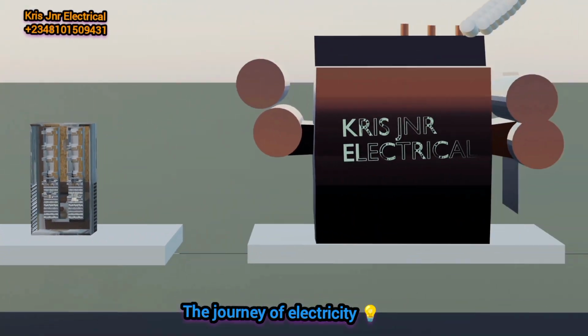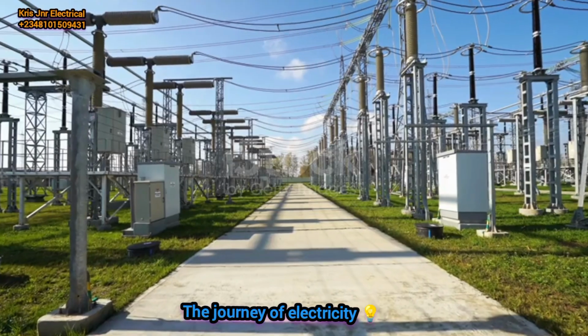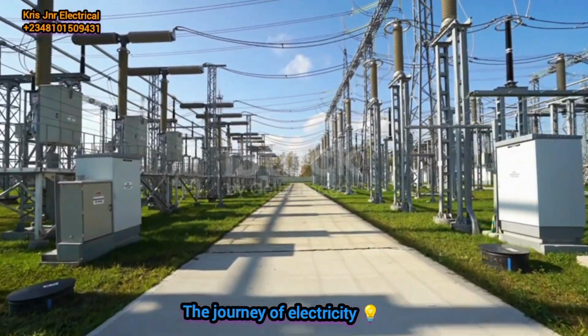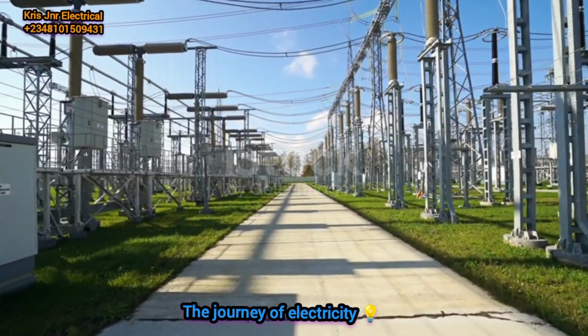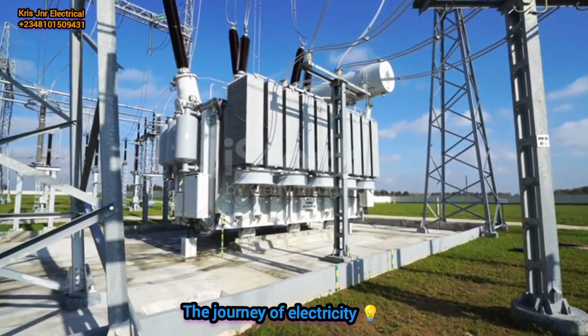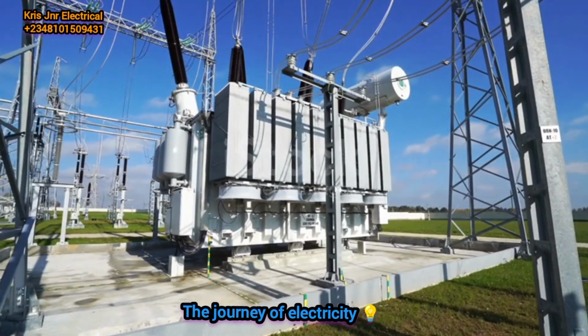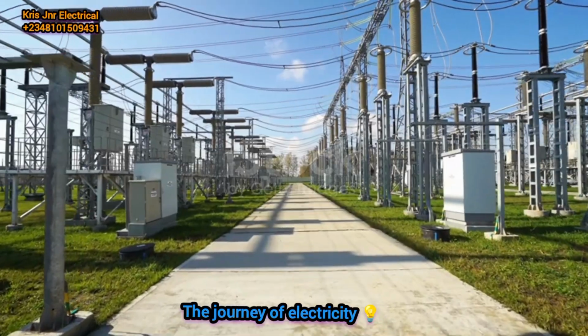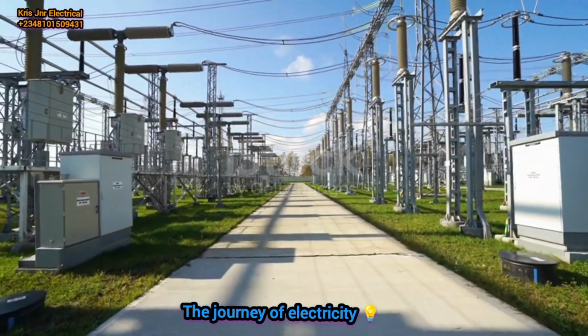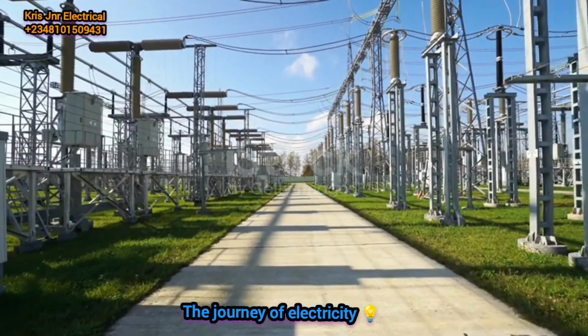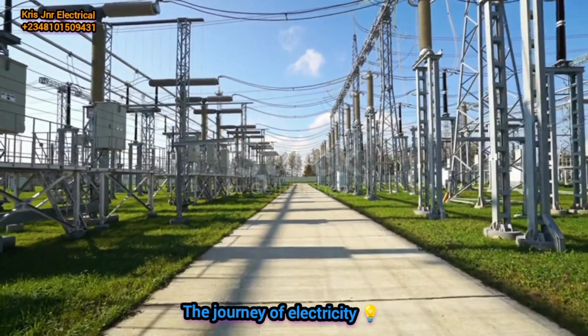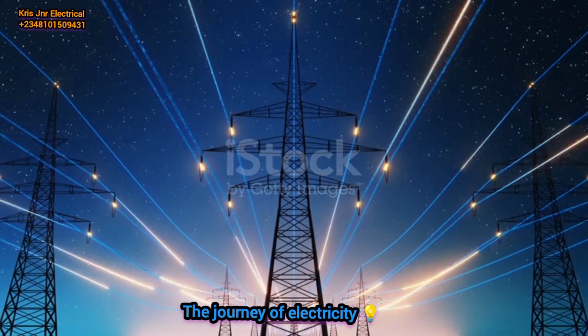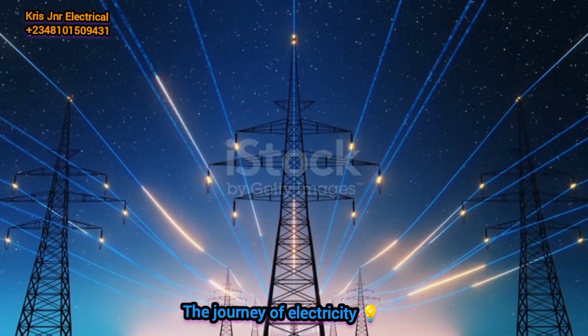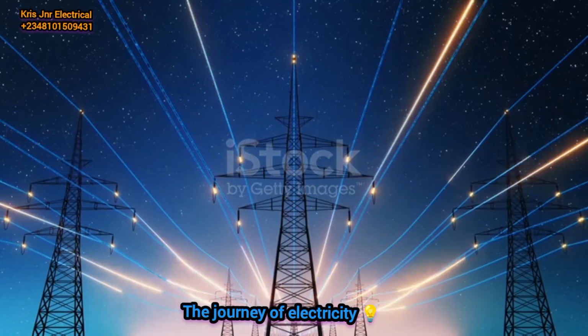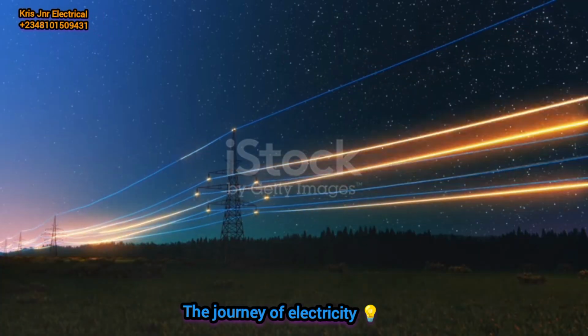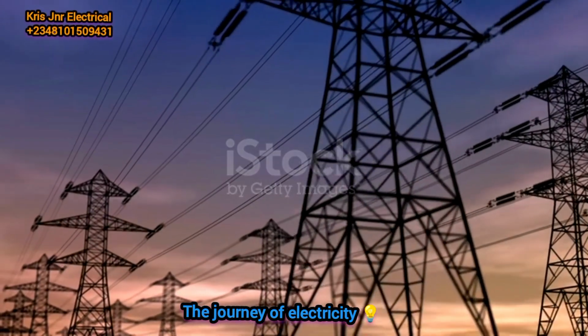So what happens is, big transformers are installed. Transformers can step up voltage. Okay, so this 11,000 volts will be connected to transformers. You can see the transformers here. So these transformers will increase the voltage to 132,000 volts or 330,000 volts, thousands of volts, before the voltage is transported along electrical conductors. All these power lines you see, they are carrying high voltages either from the generation station or maybe the distribution section. So these power lines will now travel far distances.